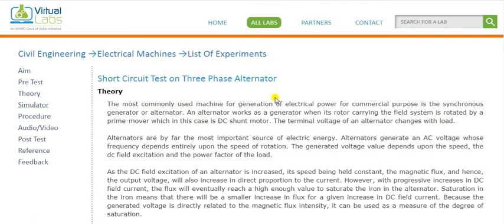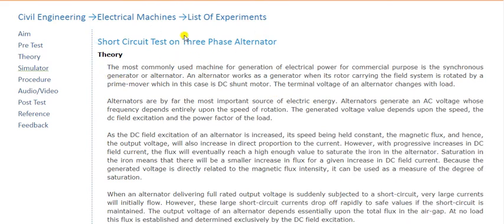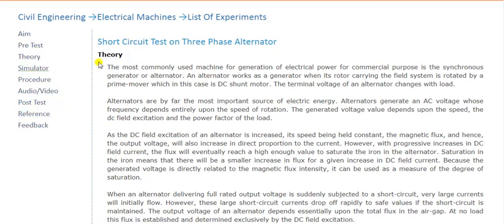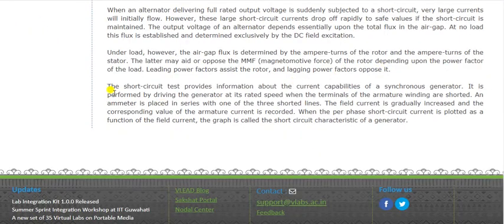Now let's see why we perform the short circuit test. In the virtual lab you can read the theory. The most commonly used machine for generation of electrical power for commercial purposes is the synchronous generator or alternator. The short circuit test provides information about the current capabilities of a synchronous generator. It is performed by driving the generator at its rated speed when the armature winding terminals are short-circuited and an ammeter is placed in series with one of the three shorted lines.